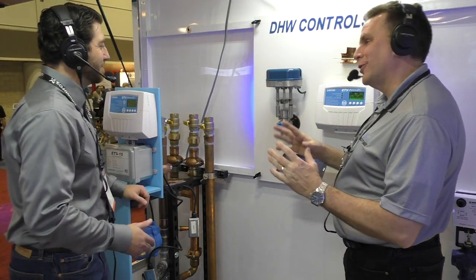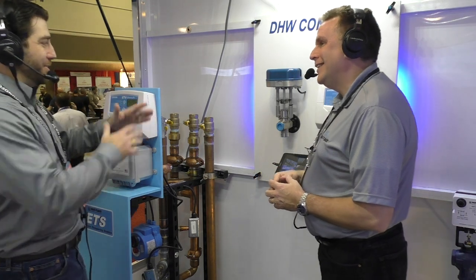So it's a great combination to be able to cover the full flow demands of the building with these systems. We don't like to say it's no maintenance, but the valve body itself is a full port valve body with a plunger in it. So there's no low orifices or anything like that where you need to worry about scale buildup occurring. So, yeah, it's basically maintenance free - as close as you can get. Still going to recommend some strainers in the piping, but overall, great - stainless steel body, full port, so that's awesome.